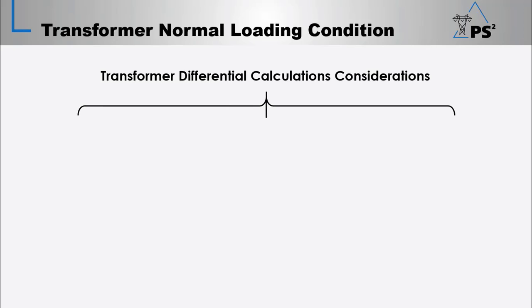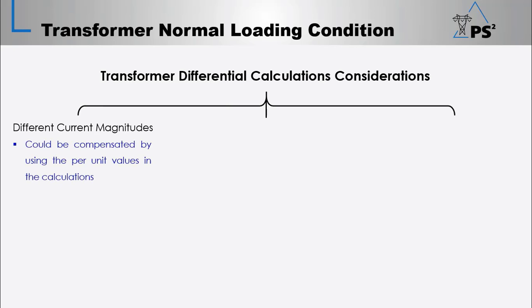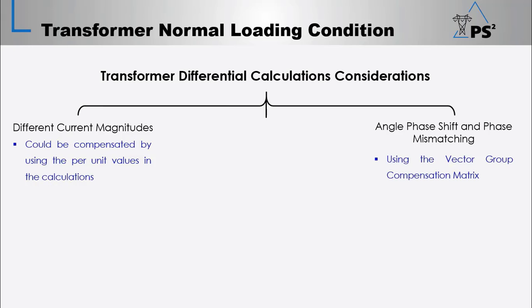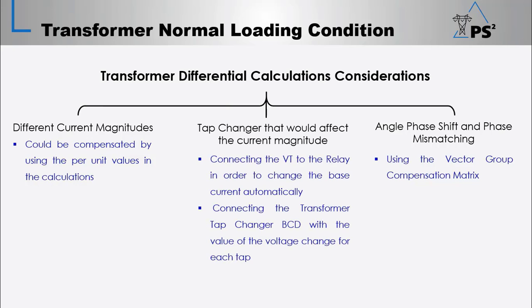From those measurement values, we must consider the following points in the transformer differential calculations: the different current magnitudes, and this could be compensated by using the per unit values in the calculations rather than using the ampere values; the angle phase shift and phase mismatching, and this could be compensated by using the proper compensation matrix; the tap changer that affects the transformer winding ratio, which affects the current magnitude at the same loading condition. And this could be compensated in two different ways: either connecting the voltage transformer to the relay and getting continuous voltage measurement and hence changing the base current value, or connecting the transformer tap changer BCD with the value of each tap voltage difference, then the relay could calculate the actual running voltage and change the base current value.